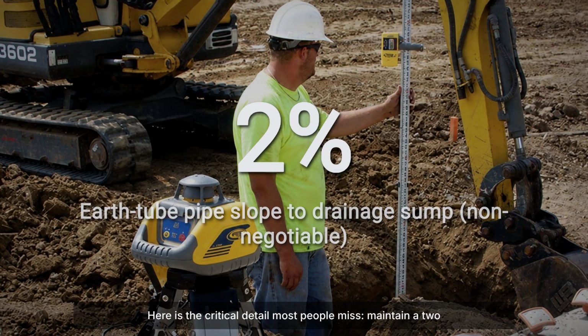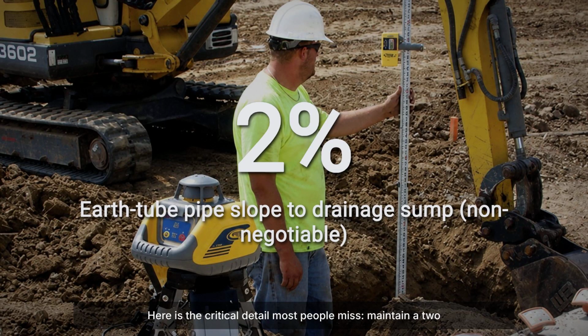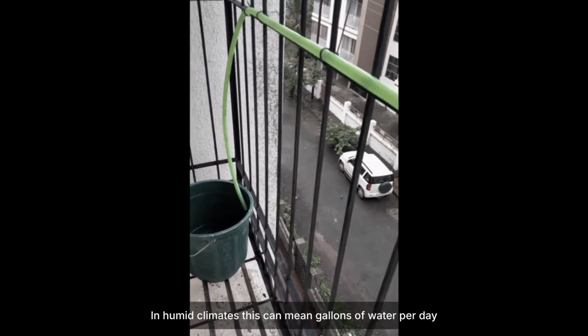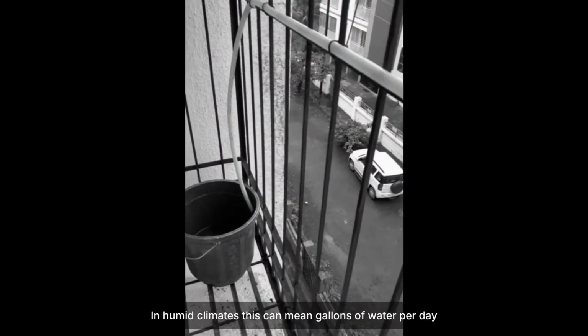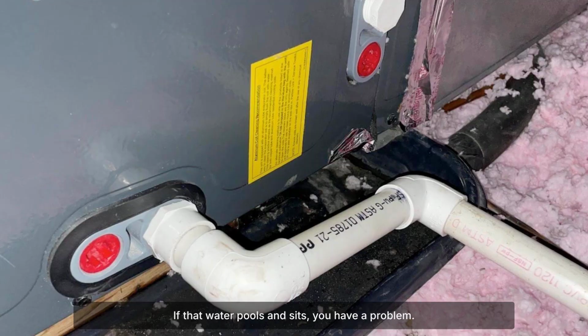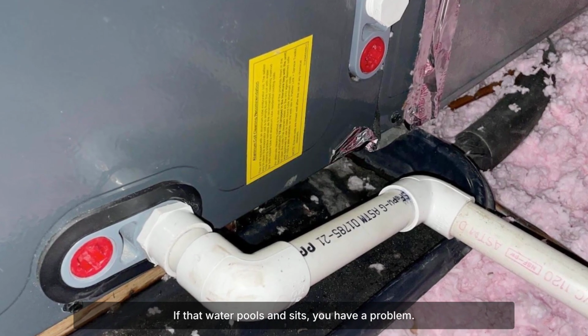Here is the critical detail most people miss. Maintain a 2% downhill grade toward a drainage sump because condensation will form inside the pipe. In humid climates, this can mean gallons of water per day collecting inside your tube. If that water pools and sits, you have a problem.